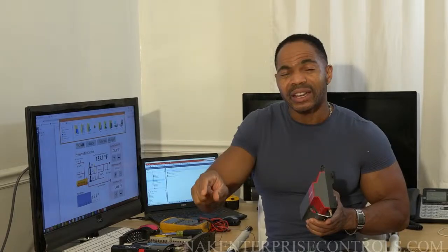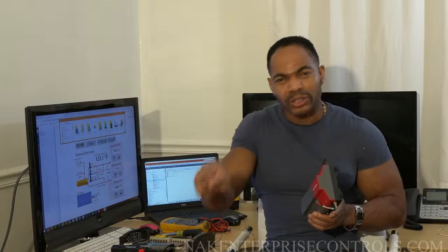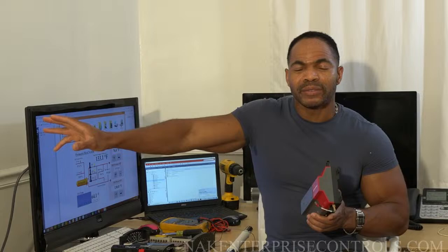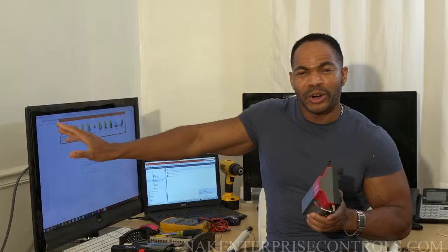You can set a set point created, where you pull a link from there to a set point, 72 degrees. So that's telling you 72 degrees is where I want things to be. So when it gets too cold, the loop then sends that signal to the valve and opens it up. And when the temperature sensor sees it gets too warm, it says, okay, I'm too warm, and sends a signal to the valve to close.